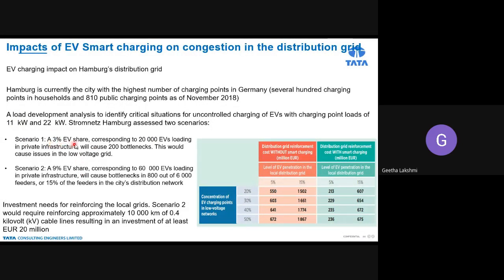Scenario 1: a 3% EV share, corresponding to 20,000 EVs loading in private infrastructure, will cause 200 bottlenecks. Scenario 2: a 9% EV share, corresponding to 60,000 EVs loading in private infrastructure, will cause bottlenecks in 800 out of 6,000 feeders, meaning 15% of the feeders in the city distribution network would be bottlenecked.